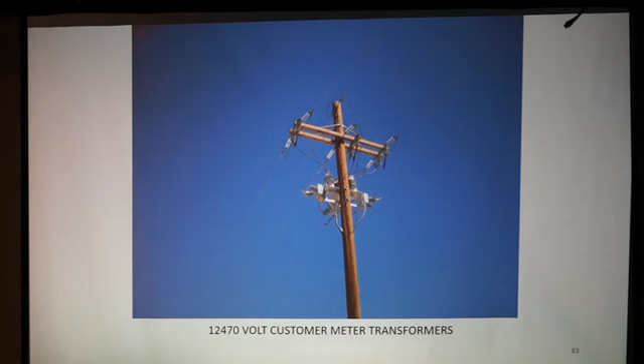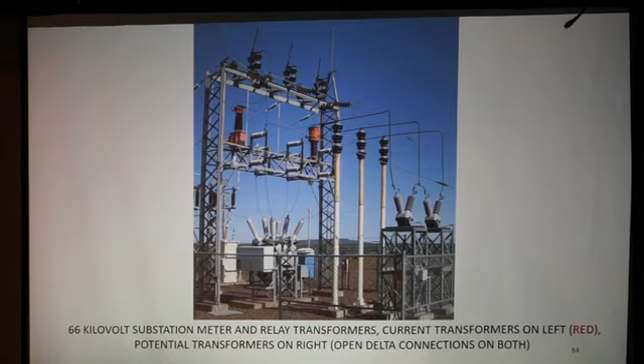Because the load is delta, the current transformers are open delta and the potential transformers are open delta. You can see the potential transformers there in the front with the two insulators, and the current transformers, the old style, up on the tower in the back in red.